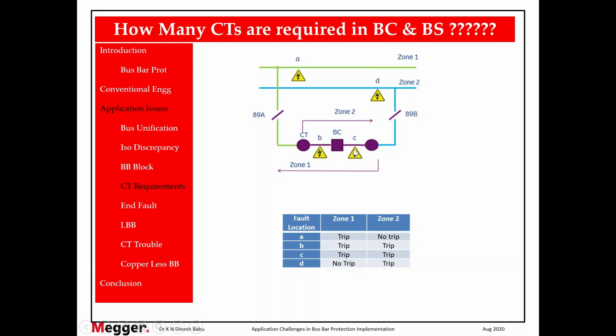Third condition, fault in location C. What will happen? Overlap region. Both zones will trip. Fault in location D. What will happen? Zone 2 will trip, zone 1 will not trip. So it's a very simple concept. Now, what happens? Conclusion. Unwanted trip of zones in 2 scenarios. What are the 2 scenarios? B and C. So for B, unwantedly I tripped zone 2. For fault at C, unwantedly I tripped zone 1. Right? So when you use the 2 CT method, this is the result. Now let us analyze with another method, 1 CT method.